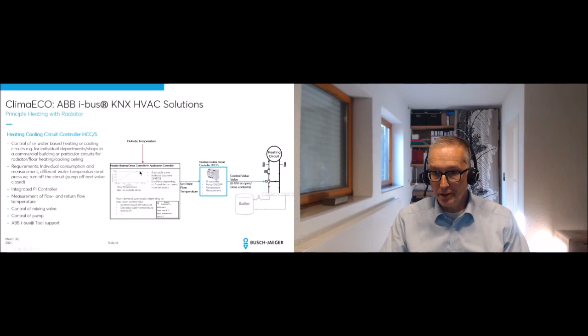That's our solution here. The boiler or chiller, I've mentioned, we can interface this. So the boiler and chiller has to provide the right amount of water for the whole system, all the circuits, all the rooms behind. And this we can interface via a 0 to 10 volt analog output in this boiler chiller interface. So also here, depending on the demand, we do the right things next to the boiler and chiller. But we do not control the boiler and chiller, so it's still a standalone component. We do not touch any internal safety mechanisms, we only say what is the right set point.